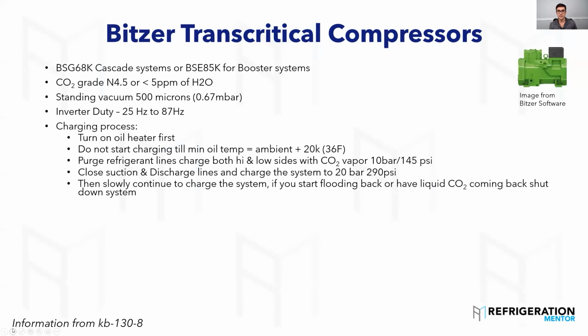Charging procedures. Bitzer wants you to turn on that oil heater first. Copeland does as well. Almost all manufacturers will say this. They want you to heat up that oil so there's no migration. What migration is that refrigerant is going to travel to the coldest part of the system. If that compressor is the coldest part, it's going to travel there. Refrigerant's also chemically attracted to oil, so it's always going to want to go to the compressor. So they want you to turn on the oil heater.